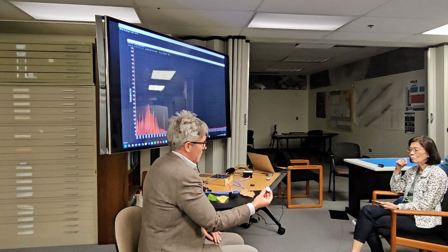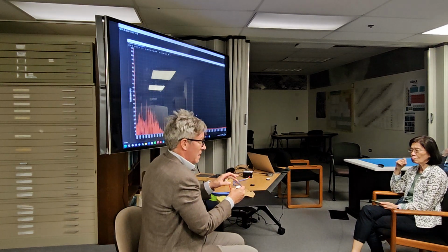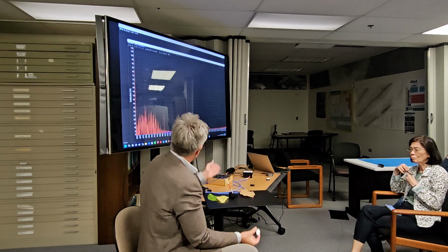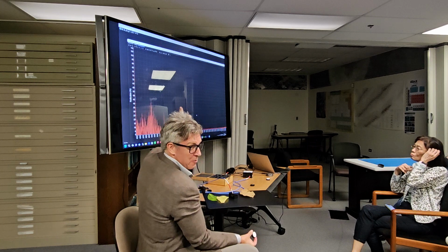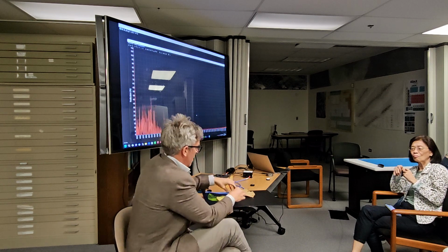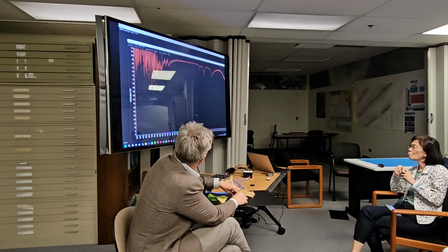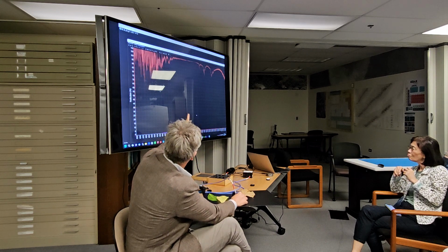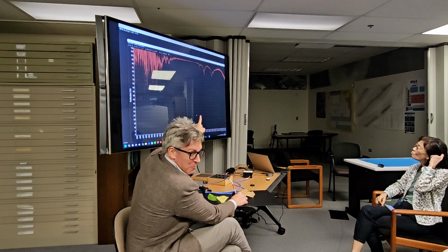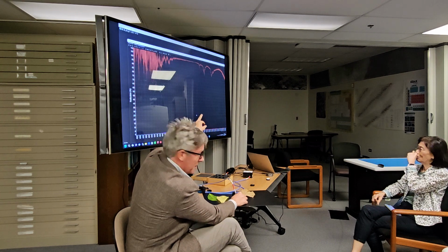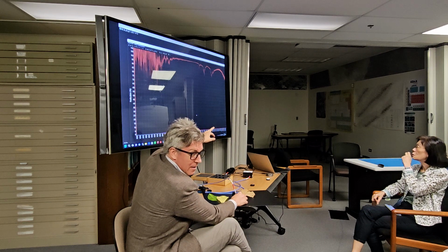Because again, this is a material that exhibits absorption peaks and troughs which correlate with its chemical composition. And I don't care what they are. What I care is I have peaks and troughs along the whole spectral range. So what I can do is say, well, I've designed a spectrometer and I want to check that it's working, right? So I put this underneath it, and I say, well, okay, this thing is reflecting a ton of light over here, but I have these absorption troughs, these reflectance troughs, right? And you can see there are a few on the right-hand side there which are especially prominent, right?